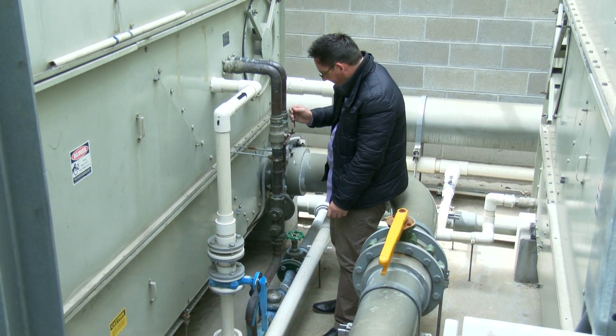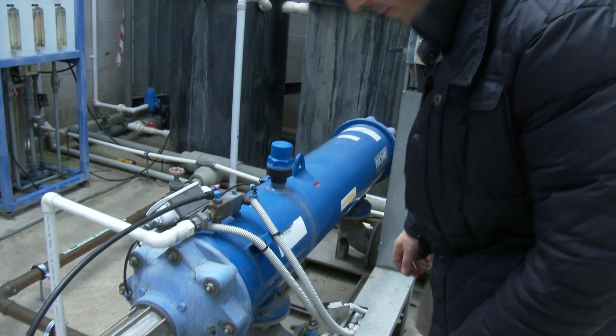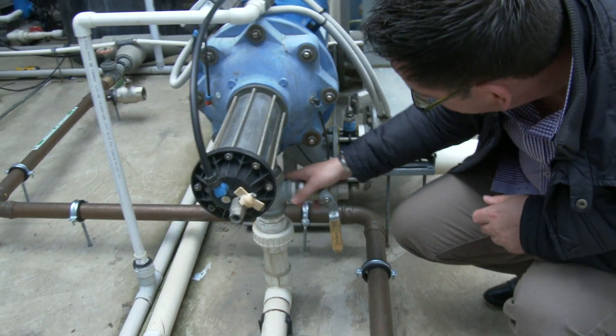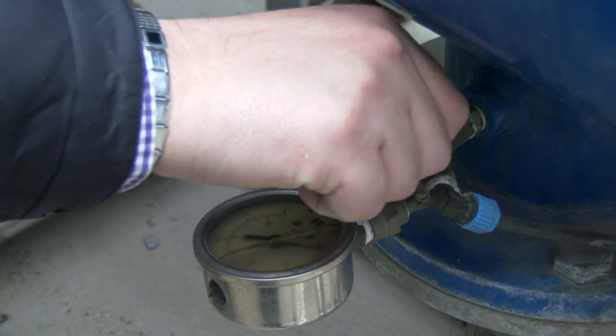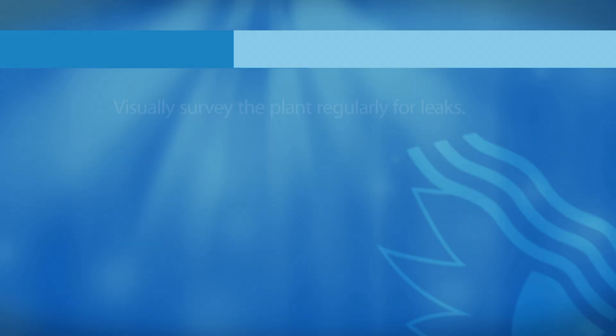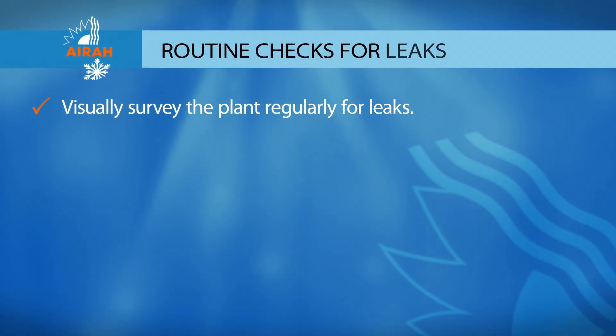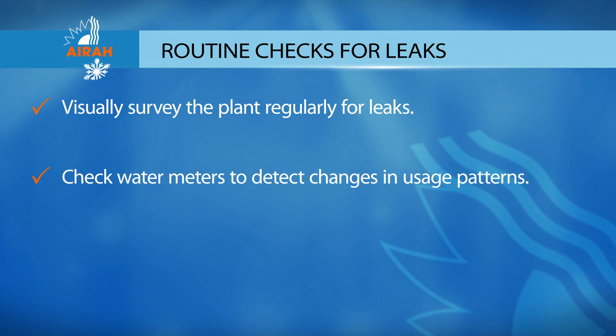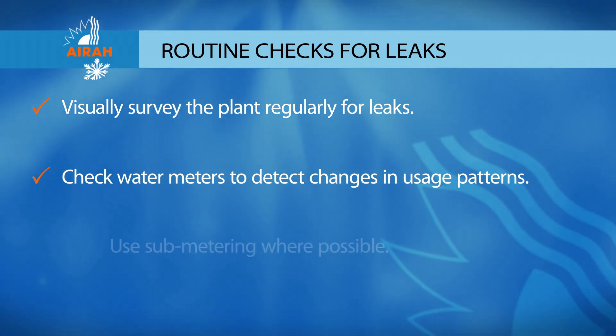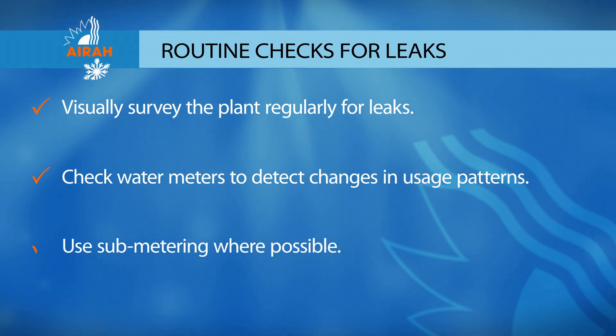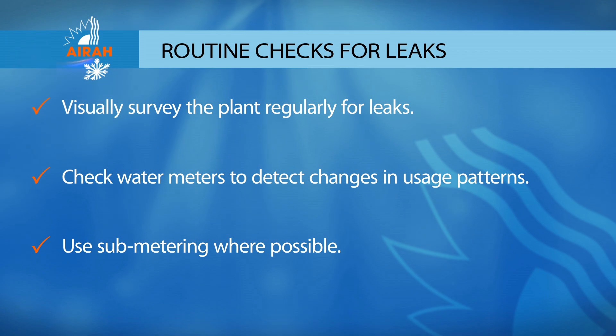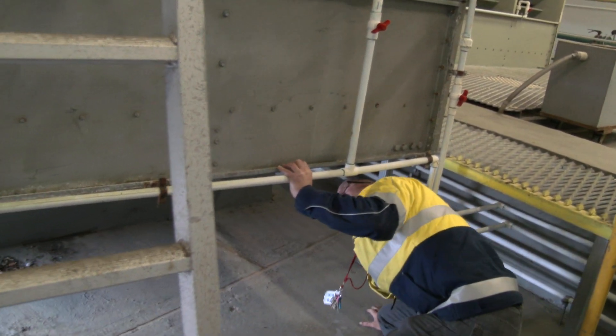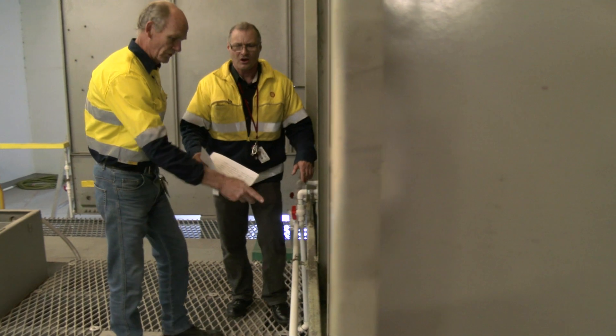Leaks can occur at any time and will disturb the balance of water treatment systems by diluting the system with more make-up water than expected. Visually survey the plant regularly for leaks. Check water meters to detect changes in usage patterns, and use sub-metering where possible. A sharp decrease in water conductivity could also indicate the presence of a leak.